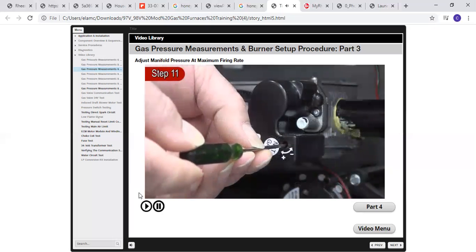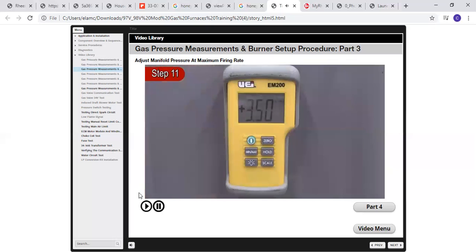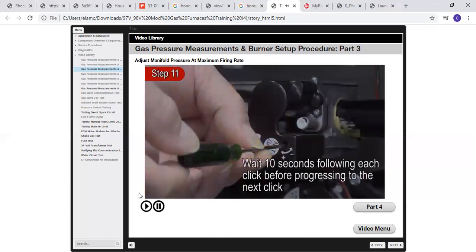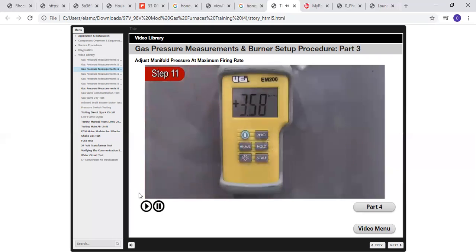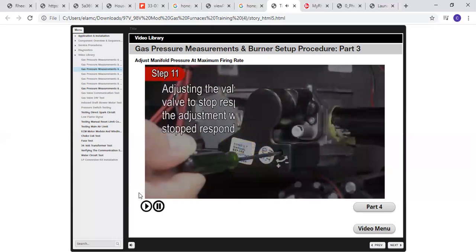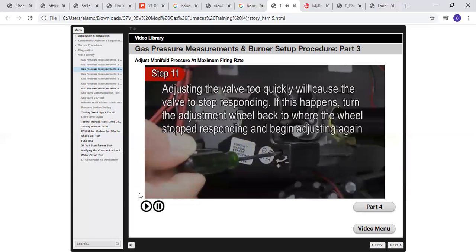Several clicks may be required to adjust manifold pressure to the necessary 3.5 inches water column natural gas or 10.0 inches water column LP for high fire. Wait 10 seconds following each click before progressing to the next click. Verify the new manifold pressure following each adjustment. Adjusting the valve too quickly will cause the valve to stop responding.